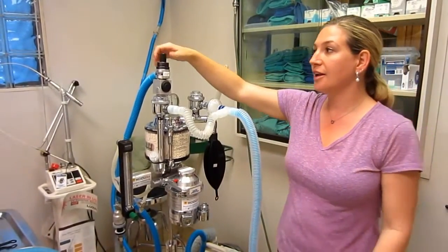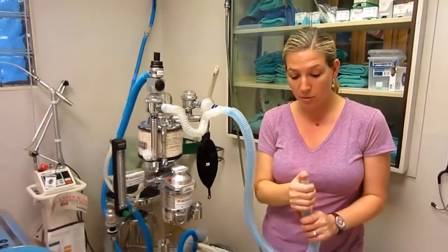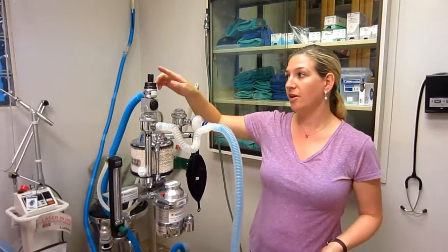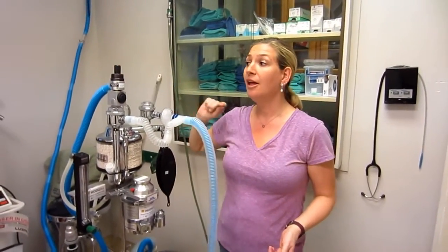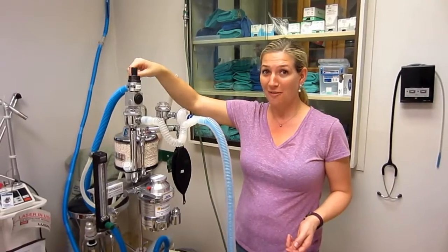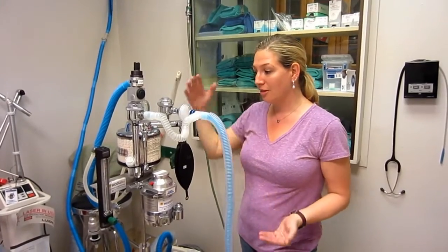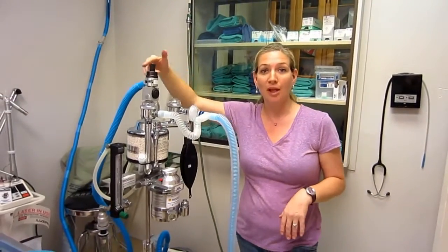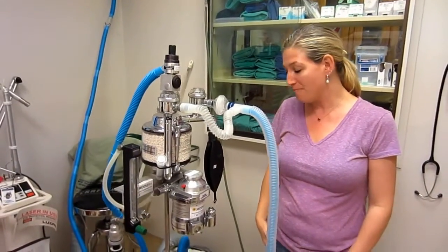And then at the end, I just want to point out again that you always open the pop-off valve. That's how you release pressure. It would be really easy for me just to let go with my thumb, and that would do the exact same thing. But you don't get the benefit of checking to make sure that this works, and that's part of your pressure check, is to open that up. The other reason is it reminds you to open it. So if you're setting up for a surgery, and this is probably one of the last things you'll do is pressure check, to remind yourself to open it up, let the air go out that way, let the pressure reduce there. So 2 benefits of that.